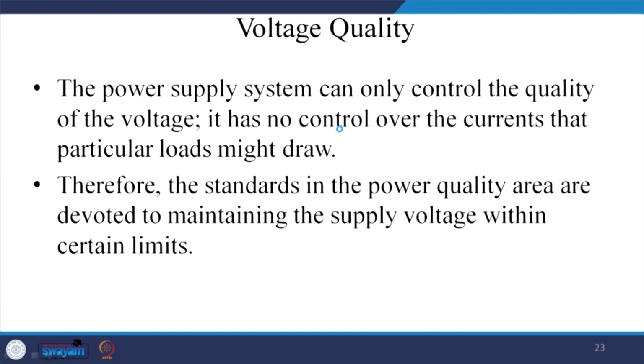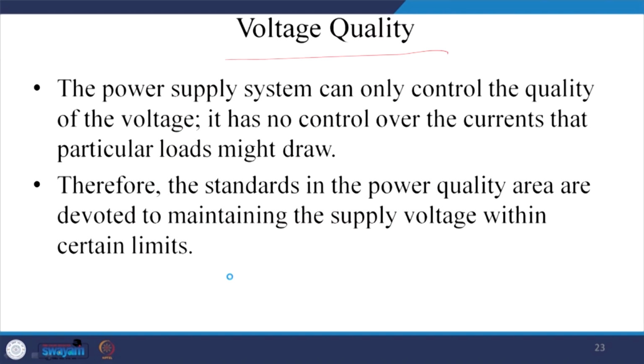Then we require to define. Because of the perception you have, you can see that there is a blame game to some extent. Customer believes that 17% of power quality problems are due to the utility, whereas the utility believes that only 1% of power quality problems are due to them, and the rest, 25%, is due to the customer. So, there is a perception difference of power quality. Thus we require a standard to identify whose responsibility it is to fix it. Otherwise, this blame game will continue.